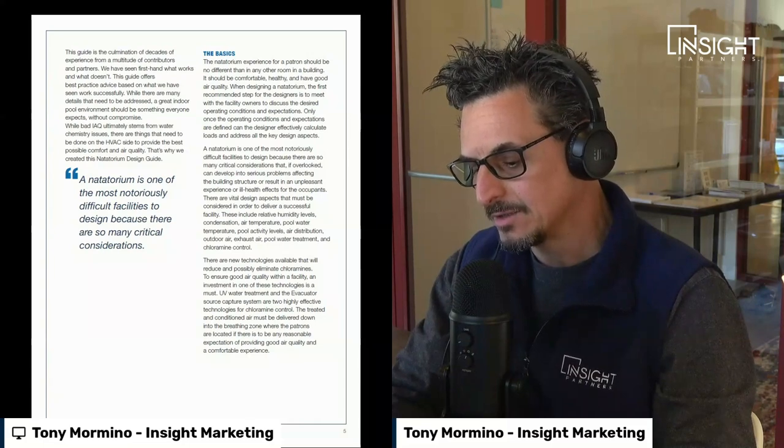There are new technologies available that will reduce and possibly eliminate chloramines. To ensure good air quality within a facility, an investment in one of these technologies is a must. UV water treatment and the Evacuator source capture system are two highly effective technologies for chloramine control. The treated and conditioned air must be delivered down into the breathing zone where patrons are located if there is to be a reasonable expectation of providing good air quality and a comfortable experience.